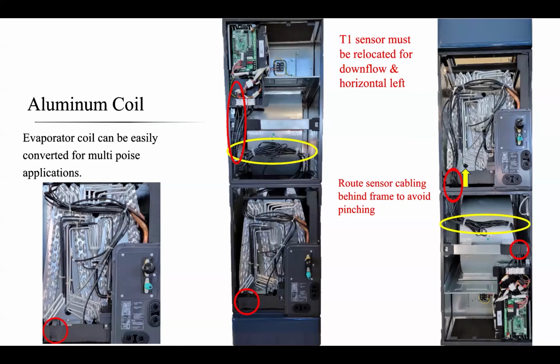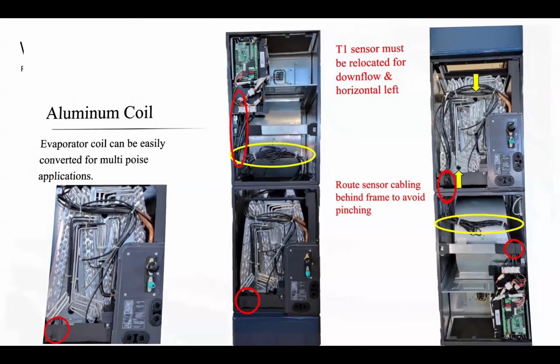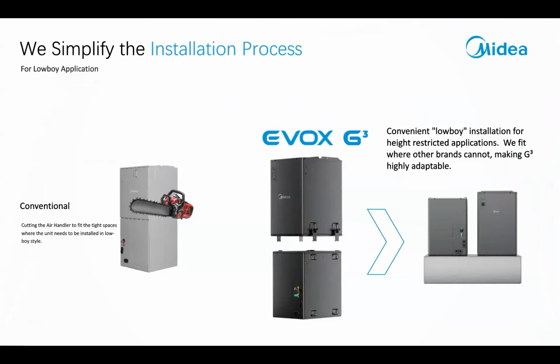There's the T1 sensor in its original form, in its original location. It has to be rerouted and put there in that rubber grommet if you do horizontal left or downflow. It's also the same with the low boy application, right? So, yes, the low boy application also requires movement of that sensor, because remember, your airflow is now going to be coming in through the top instead of the bottom. So low boy application also requires that.